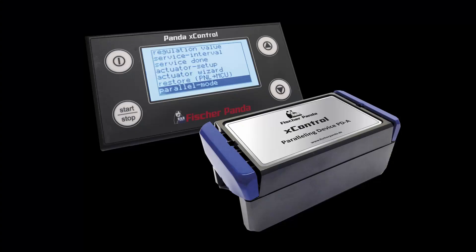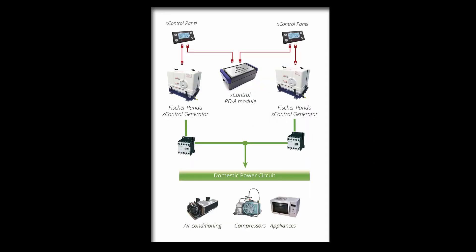Fischer Panda builds two types of generators that produce alternating current. The first type is the X-Series generators, which are regulated asynchronous generators. To connect them in parallel, a module is required — this module is available from Fischer Panda. You can simply connect both generators together and then set the generators to parallel mode using the digital display.